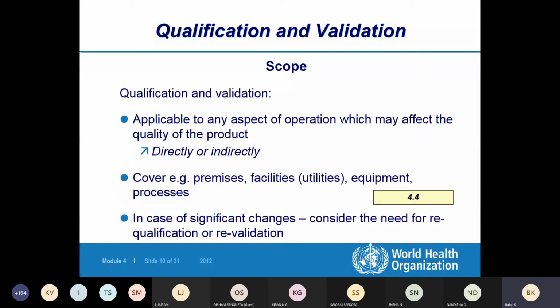Accordingly, you have to subject your equipment to validation. Once the equipment successfully meets the acceptance criteria for the output of the validation, then you can go and update your procedure: yes, this existing model of autoclave is also capable of performing this 135 degree centigrade sterilization process. This is the significant change that needs to be requalified or revalidated.